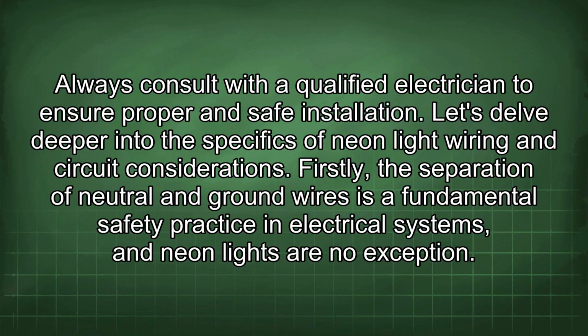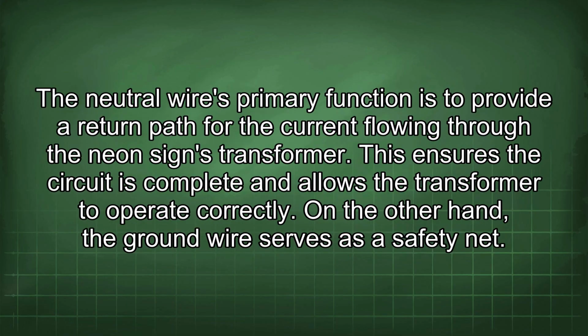Let's delve deeper into the specifics of neon light wiring and circuit considerations. Firstly, the separation of neutral and ground wires is a fundamental safety practice in electrical systems, and neon lights are no exception. The neutral wire's primary function is to provide a return path for the current flowing through the neon sign's transformer. This ensures the circuit is complete and allows the transformer to operate correctly.